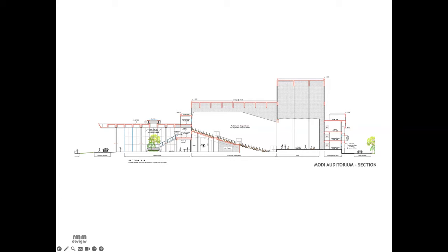The reason why I'm saying AHU use is because if you have AHUs at the bottom, you kind of get an ideal air conditioning flow. So you can have all your return air taken either from the seating, the floor of the steps, or from the side walls, the skirting level at the side walls. And you can have your air conditioning through from the top. So you get a natural ideal circulation, with cold air being thrown from the top and getting sucked in as the return air from the bottom.